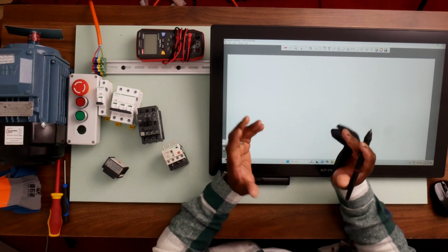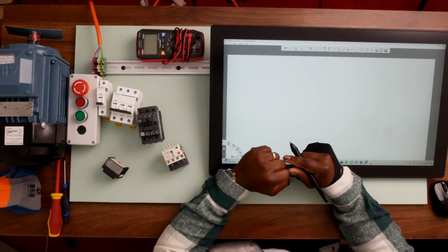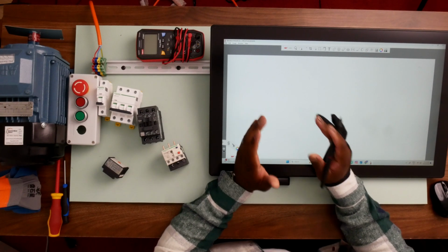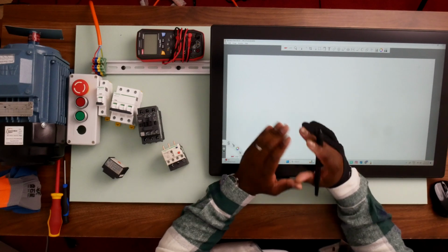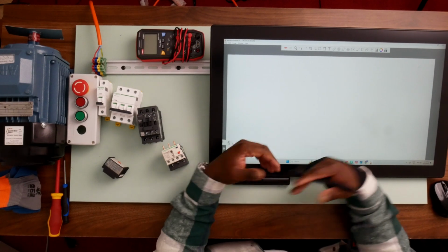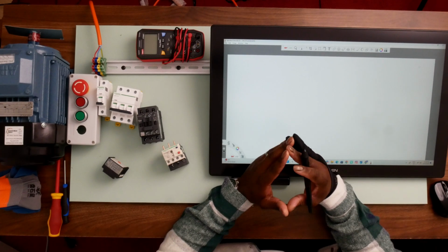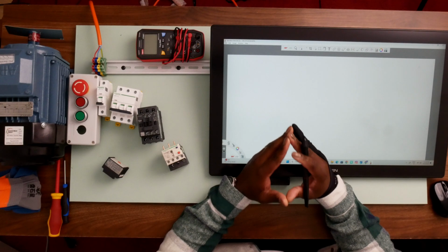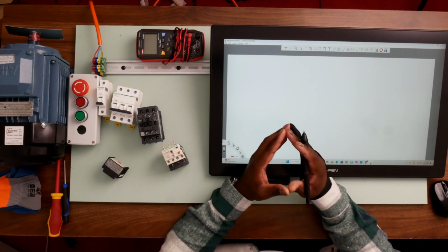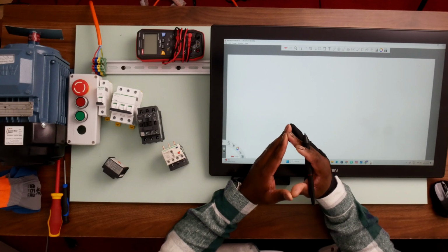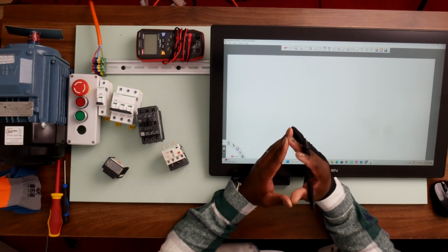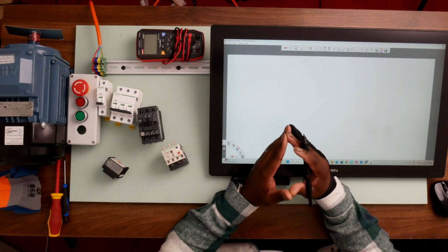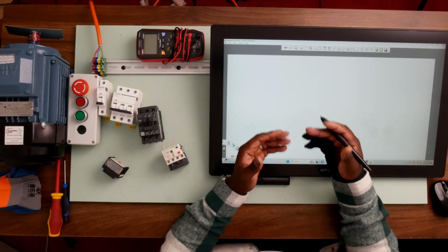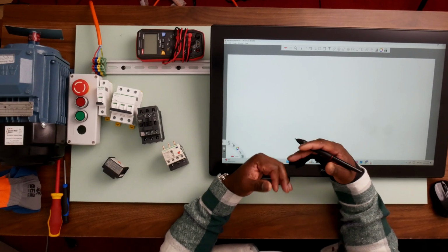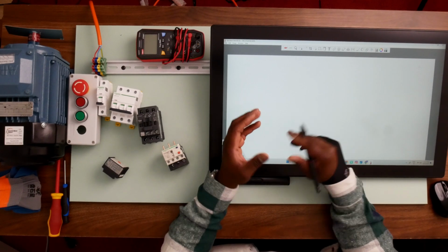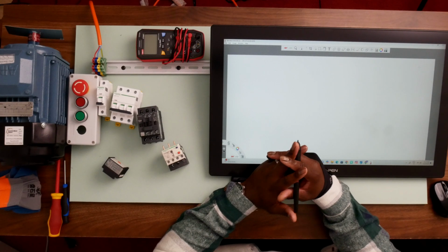All right, now that we've discussed the electric motor, let's go to the next component, which is the emergency stop button. The emergency stop button belongs to the control circuit only. It's not part of the power circuit, it's just part of the control circuit. For emergency stop buttons in a direct online circuit we use the normally closed contact. That doesn't mean that that's the only contact that you can use for emergency stop buttons, but for this purpose we are going to be using the normally closed contact, and it's the most common contact that we use on an emergency stop button. We use the normally closed contact to allow the flow of current during normal operation and only interrupt the flow of current during an emergency.